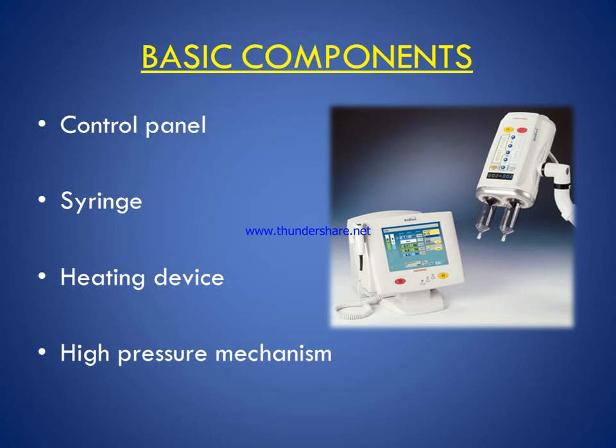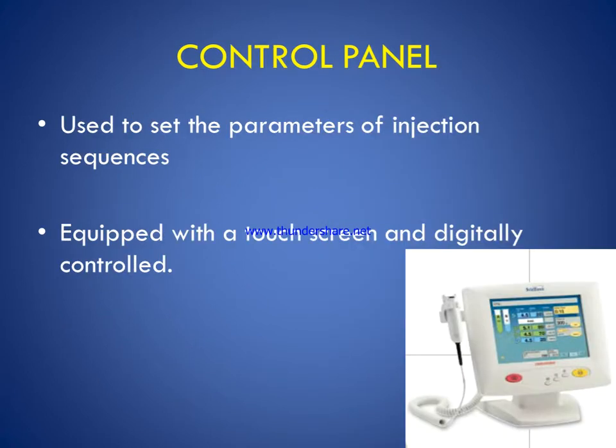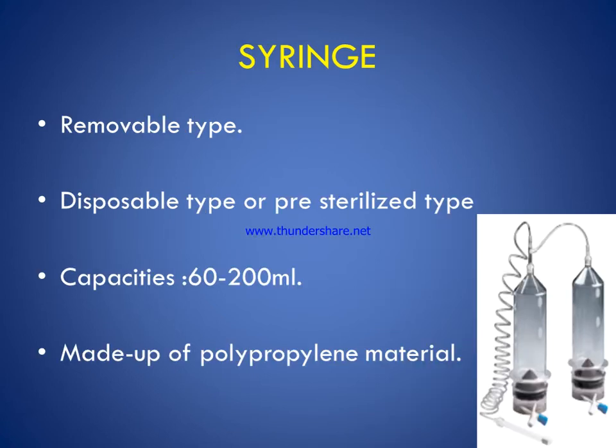The basic components of the pressure injector include the control panel, syringe, heating devices, and high pressure mechanism. The control panel is used to set the parameters of the injection sequences and is equipped with a touchscreen and is digitally controlled. The syringe is a removable, disposable, or pre-sterilized type.